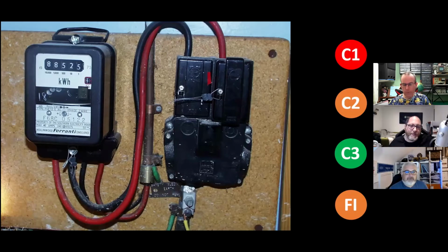Right, this one. This was in a flat that I lived in for about 3 years, and this was on the ground floor, and the flat was on the second floor. So this is the cutout, the meter, and the connection via that thing in the middle, which went upstairs 2 floors to the ancient Wylex fuse box that was in the flat. And it's another one of these 40 amp meters, which obviously isn't particularly adequate for much these days.